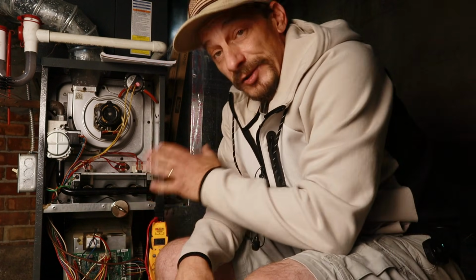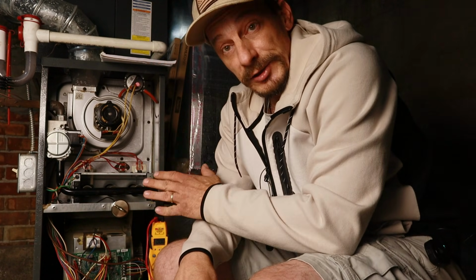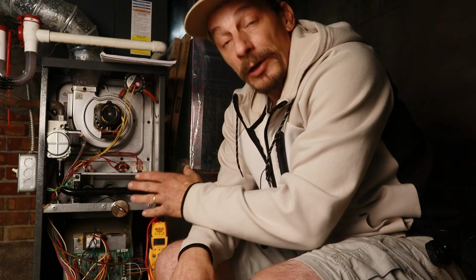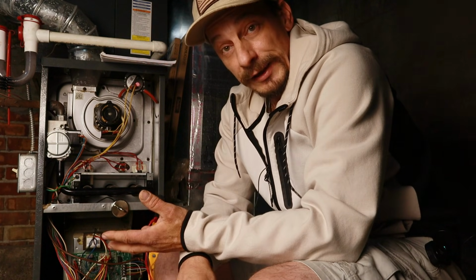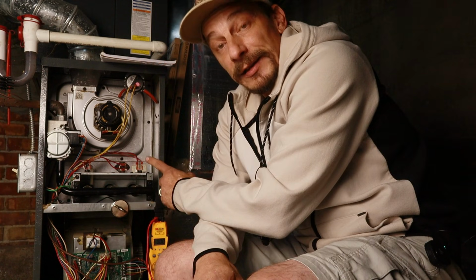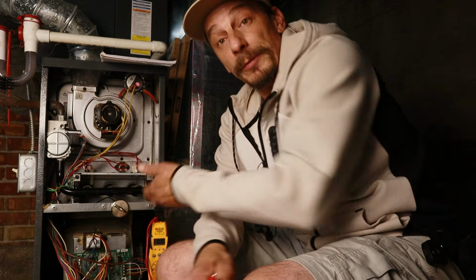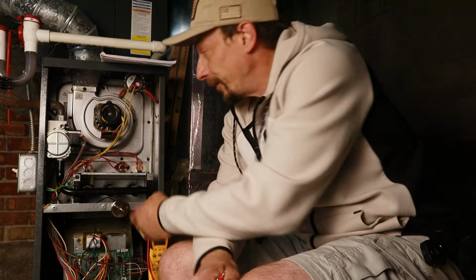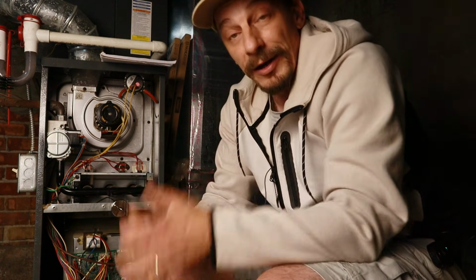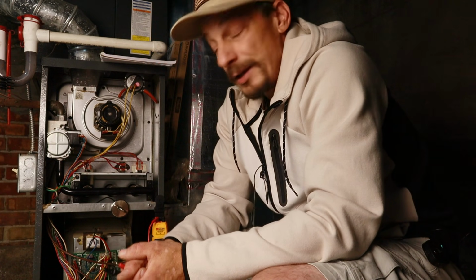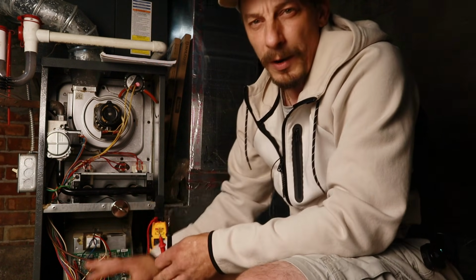Now keep in mind, this is how the furnace is wired. So even in cooling season, air conditioning is hooked up to this as well. So even when your air conditioner is running, these safeties still apply. The heating safeties are still in the circuit and they're still playing their roles. So say, for example, your air conditioning system is running, your blower motor is overheating, it's starting a fire, that thermal limit there might pick that up and shut the whole thing down. So it doesn't actually have to be in heating mode for these heating safeties to play a part in the operation of the system. So that's basically what makes all this wiring complicated.